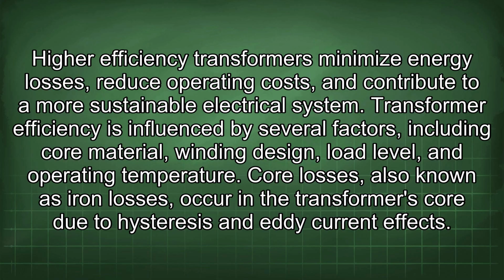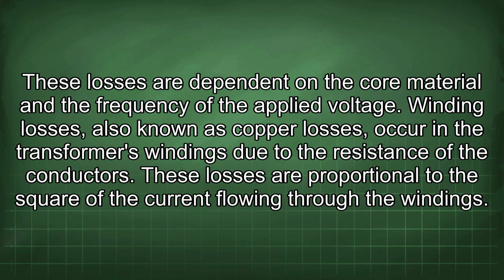Core losses, also known as iron losses, occur in the transformer's core due to hysteresis and eddy current effects. These losses are dependent on the core material and the frequency of the applied voltage. Winding losses, also known as copper losses, occur in the transformer's windings due to the resistance of the conductors. These losses are proportional to the square of the current flowing through the windings.